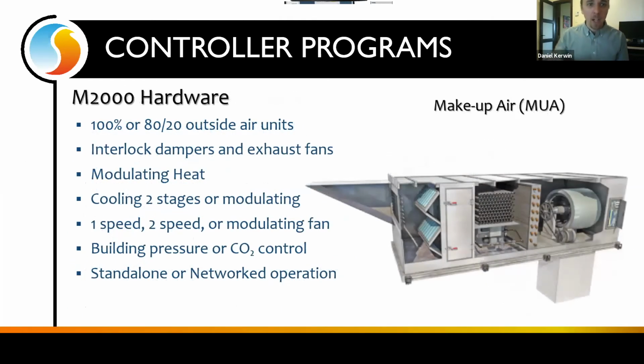For makeup air units, in case the unit is 100% fresh air, we know that the sequences aren't quite the same. I've seen people trying to use a simple thermostat to control a makeup air, and we all know that simply does not work. It needs its own dedicated sequence. So it comes with all the necessary interlocks in terms of the exhaust fans and the outside air damper and the fan status and so on.